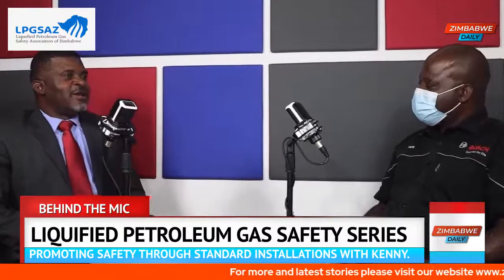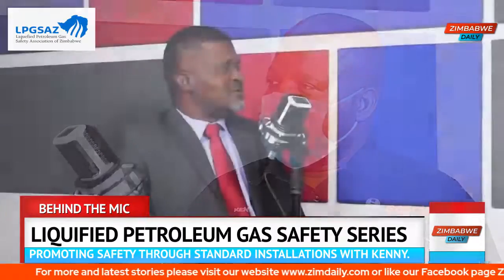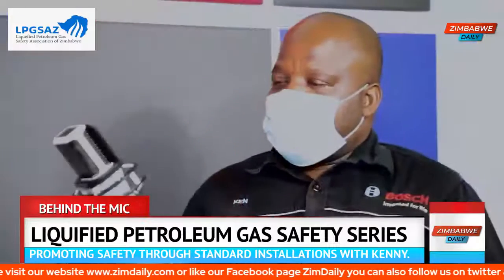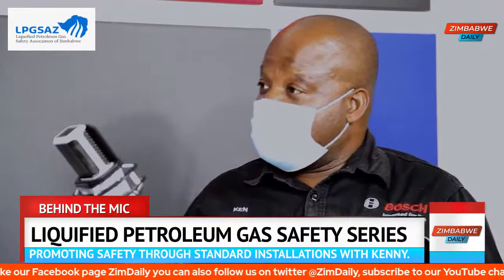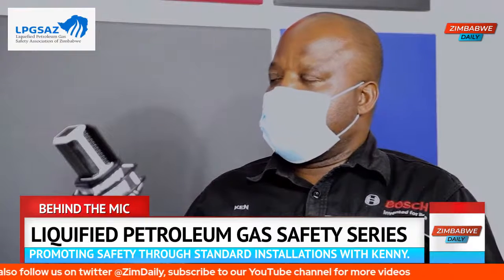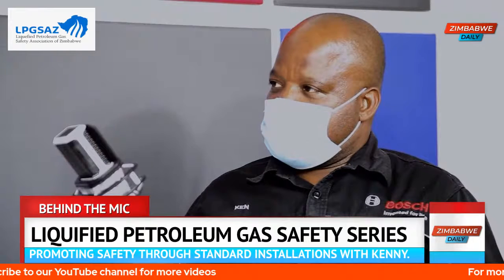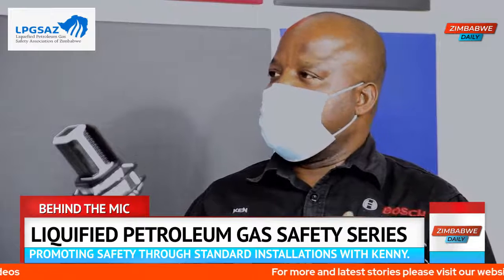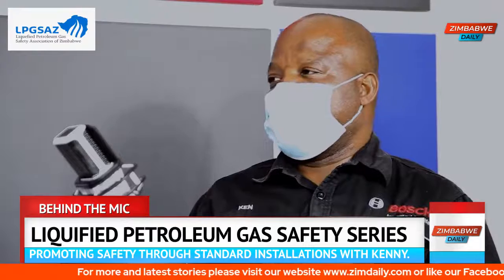Now, Kenny, have we had any instances or accidents caused by poor installations? Absolutely. We face a lot of different situations. I'll give you two in particular which are relevant in the case. One is the incorrect installation of termination of the gas appliance. So you've done everything, you've run your pipe, and coming to the appliance, the supplier will tell you, do not use thread tape.